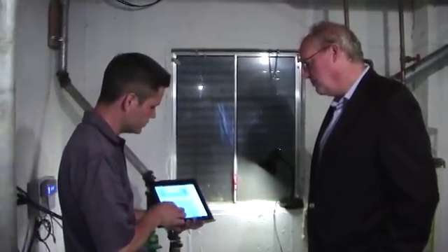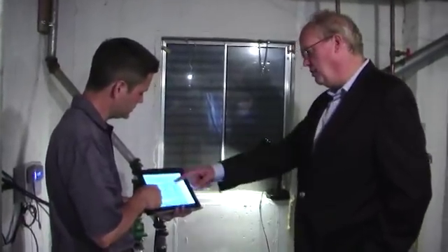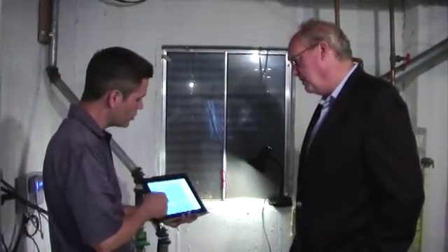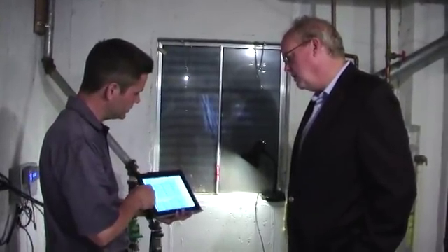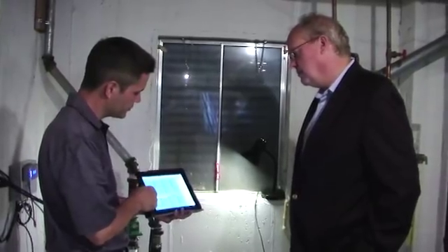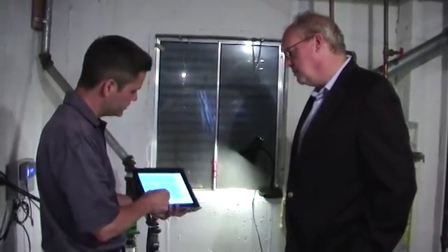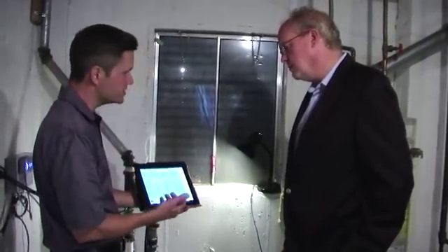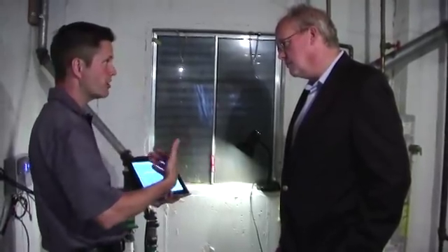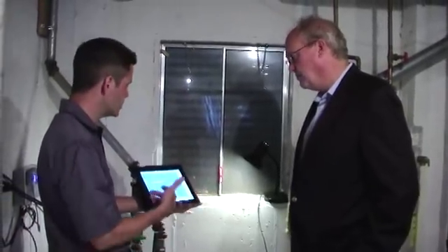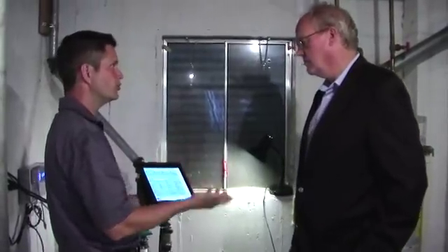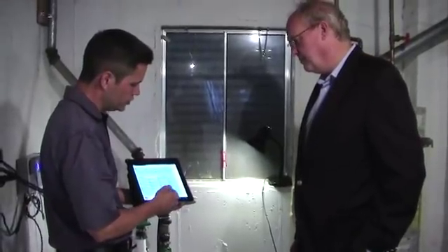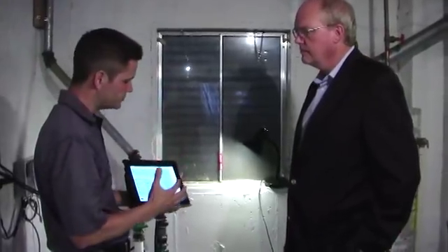The last tab is Emails. It goes through a sequential list of who it's going to contact — email number one, email number two, and email number three. Each email can be customized, so one email could get certain alarms and not others. You could put a text address in here — maybe you only want a text if something is urgent. You'll also get an IP email if your IP address ever changes with your ISP.